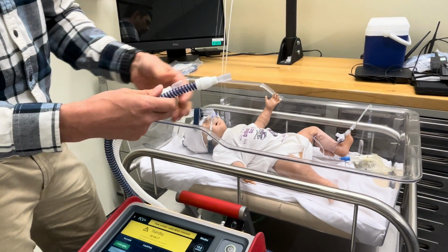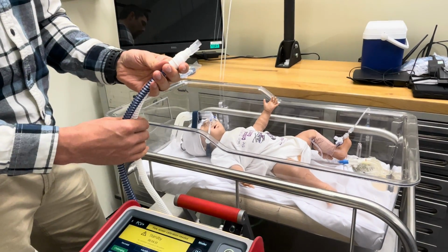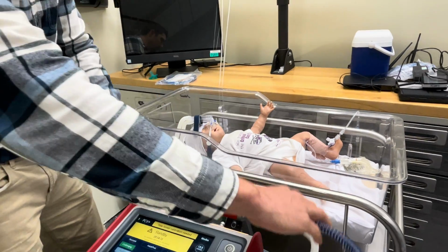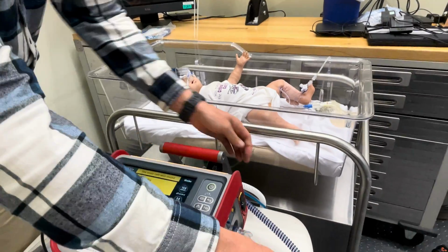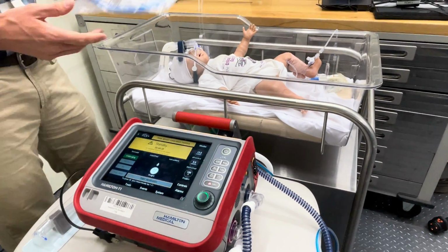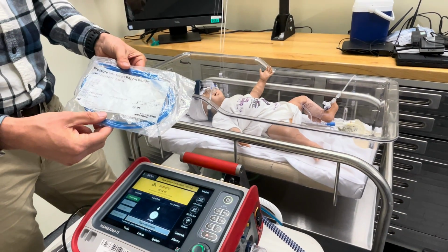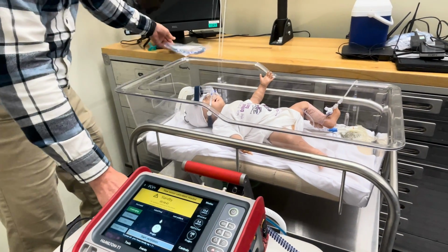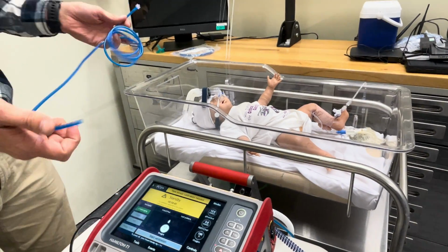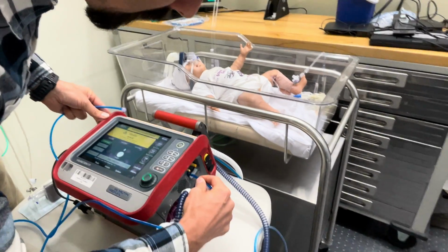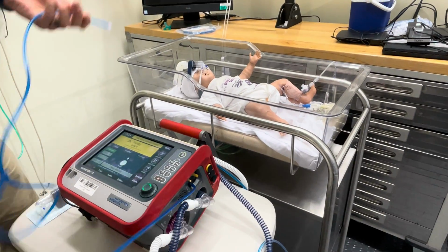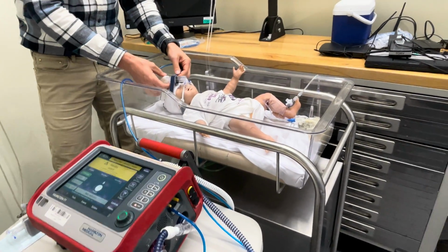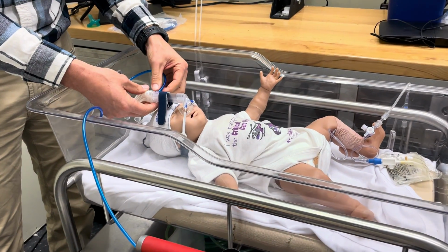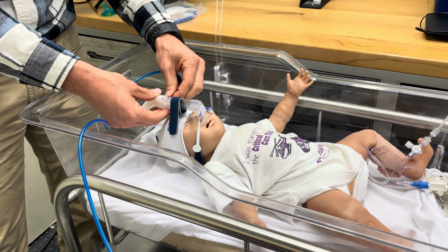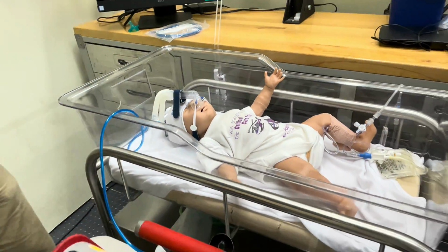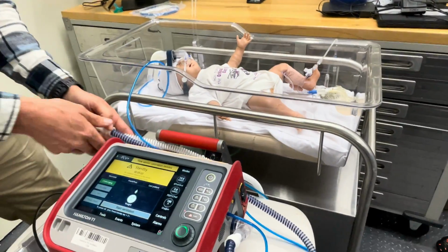But if you don't have a flow sensor, you need something to sense the pressures. And so that's the next component you're going to need. We're going to take off the flow sensor, and we're not going to use that. And in every neonatal circuit, you have this little package, which we almost never use, and it's used for this situation. It's just the blue line that connects to the blue pressure port, and it will then in turn connect to the side of the nasal interface, and it's going to measure your pressures right there. So before we switch them, what we'll need to do is calibrate our new circuit.